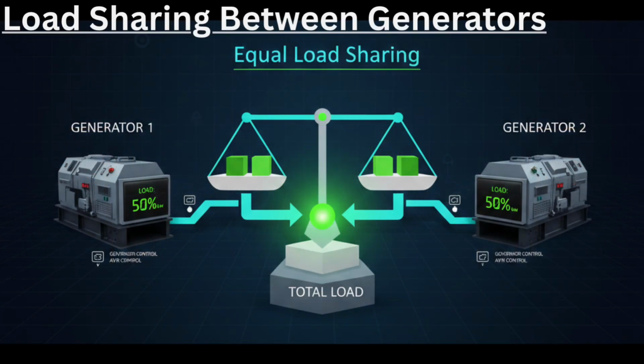Load sharing between generators. When two or more generators operate together, load sharing becomes very important. Load sharing ensures equal distribution of power between generators. There are two types of load: active power, measured in kilowatts, and reactive power, measured in kilovolt ampere reactive. Active load sharing is controlled by the engine governor, which adjusts fuel supply. Reactive load sharing is controlled by the automatic voltage regulator, or AVR.